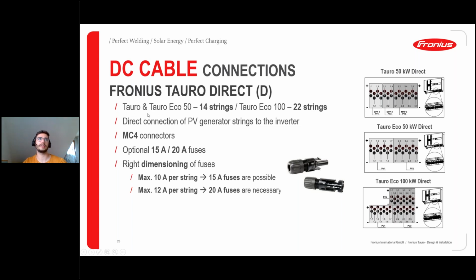And on the Tauro standard and the Tauro ECO 50, we have 14 strings. And on the Tauro ECO 100 kilowatt device, we have 22 strings. So on the far right, we can see here how it's looking like. On the 50 kW device, we have 3 MPP trackers, as we recall, and we have those connections available here. On the 50 ECO, we have only 1 MPP tracker, but it's split up in PV1 and PV2. This is just because of the DC disconnectors. So we have 2 DC disconnectors on this product. And on the Tauro ECO 100, we would have 3 DC disconnectors. That's the reason why it's split up in 3 parts here. However, we only have 1 MPP tracker available and 22 string connections.